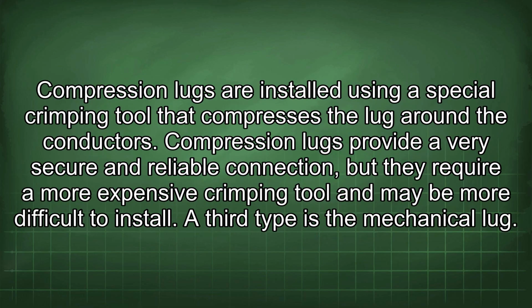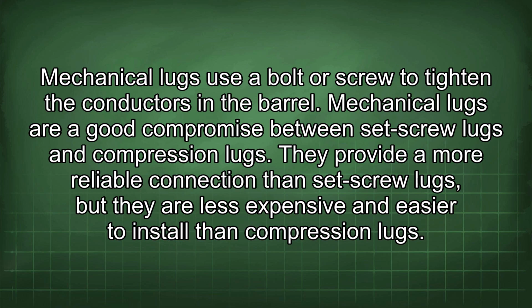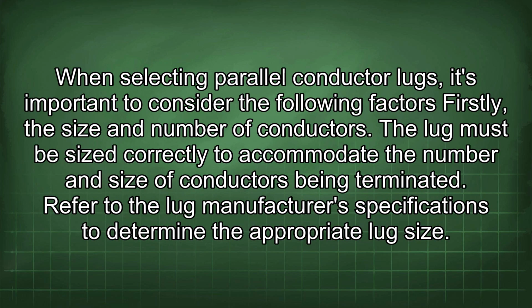Compression lugs are installed using a special crimping tool that compresses the lug around the conductors. Compression lugs provide a very secure and reliable connection, but they require a more expensive crimping tool and may be more difficult to install. A third type is the mechanical lug. Mechanical lugs use a bolt or screw to tighten the conductors in the barrel. Mechanical lugs are a good compromise between set screw lugs and compression lugs. They provide a more reliable connection than set screw lugs, but they are less expensive and easier to install than compression lugs. When selecting parallel conductor lugs, it's important to consider the following factors.